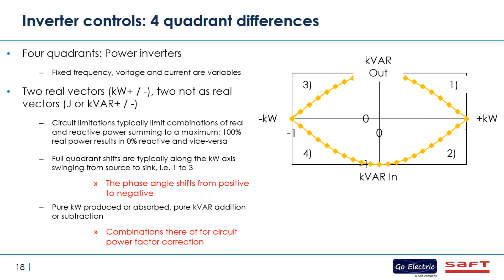Full quadrant shifts are typically along the kilowatt axis. So from, say, 1 to 3, from source to sink, and the phase angle shifts from positive to negative. Pure power in kilowatts can be produced or absorbed, and pure kVAR can be added or subtracted, or any combination thereof. So operation anywhere inside the ellipse on the right allows the inverter to enhance the system by providing different levels of both power and reactive current.